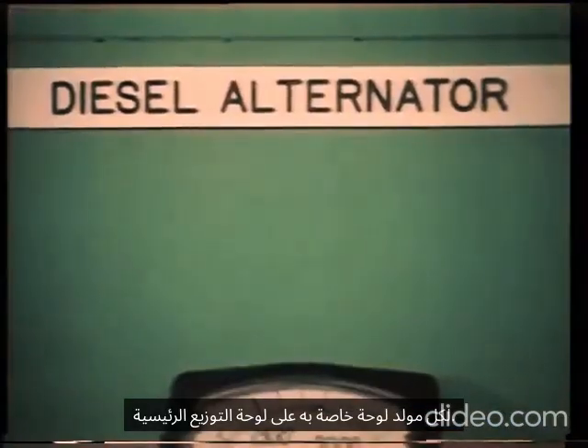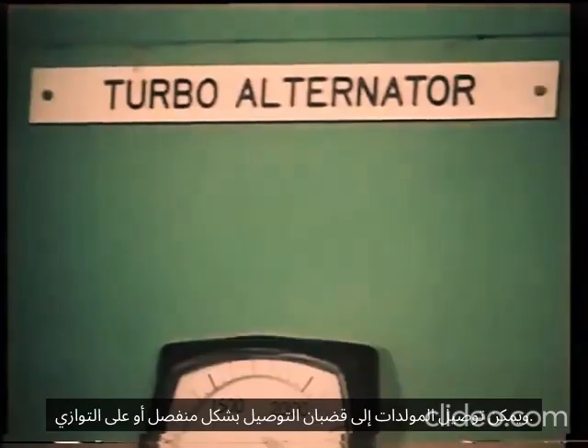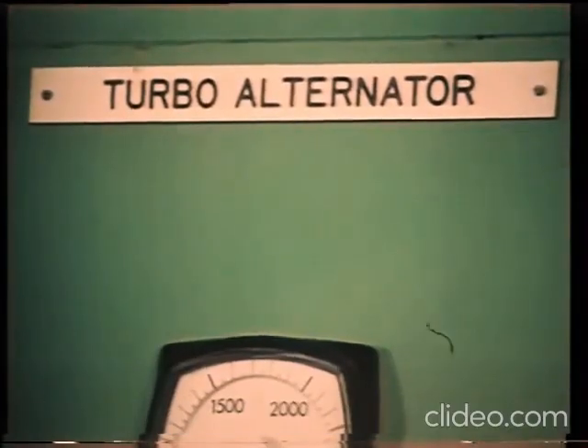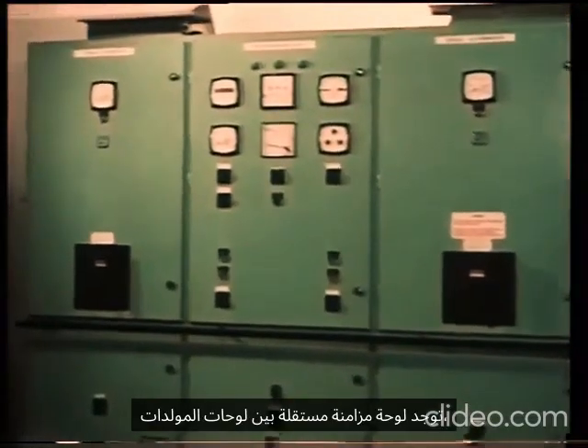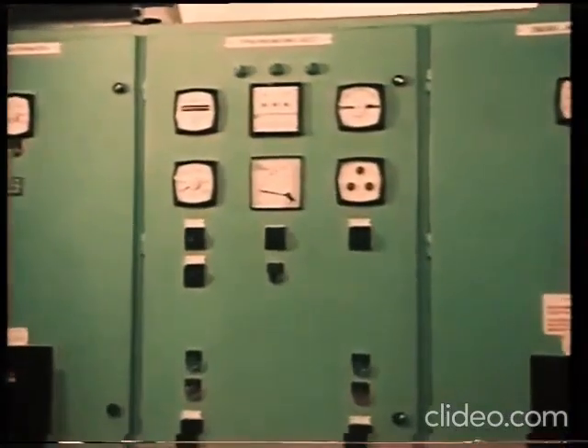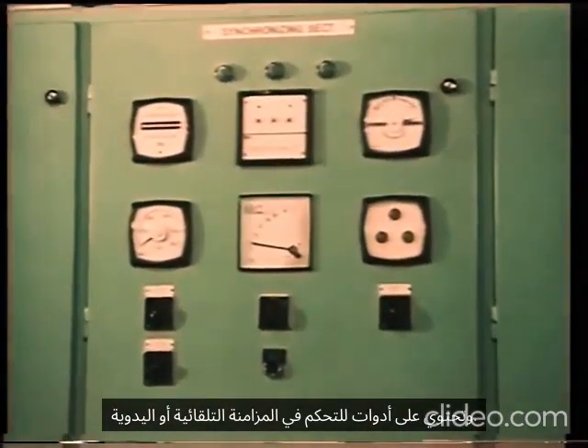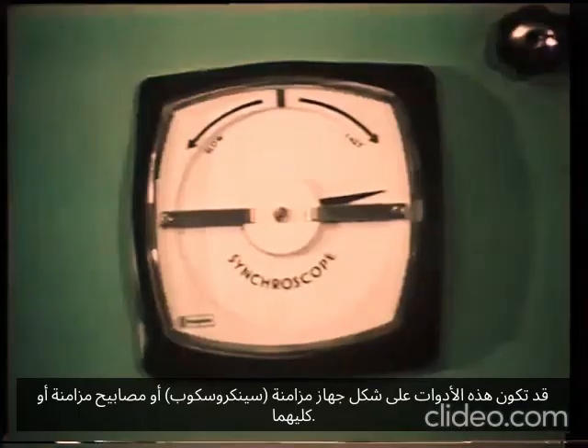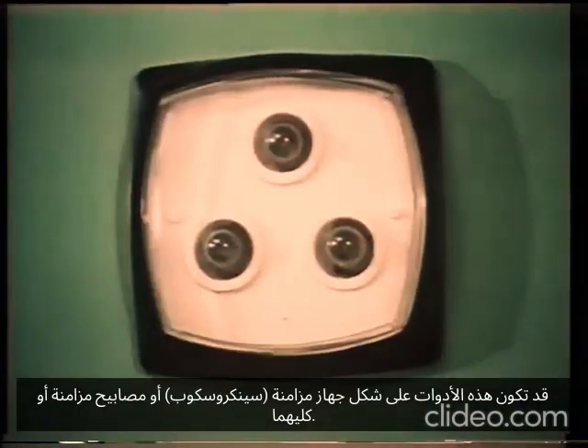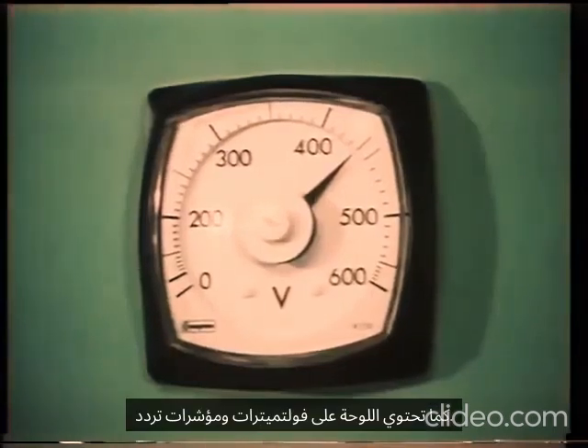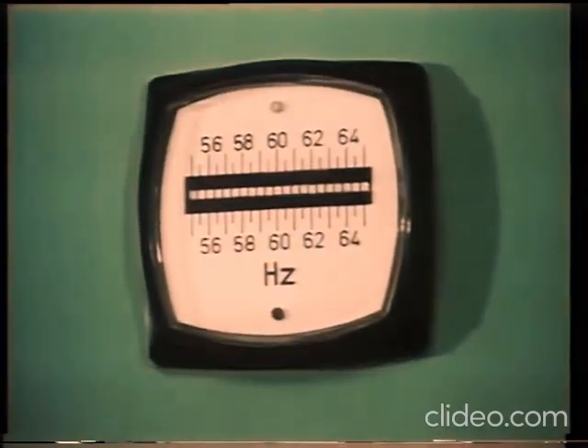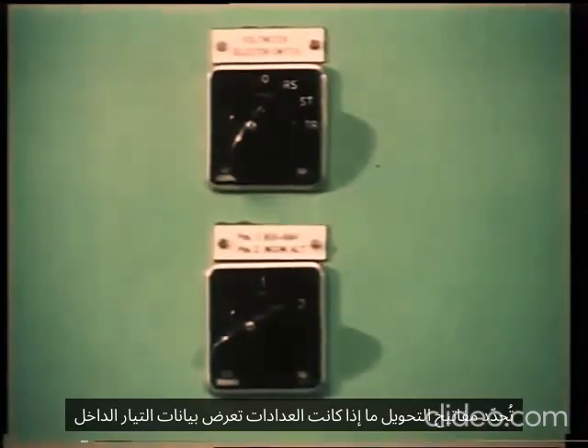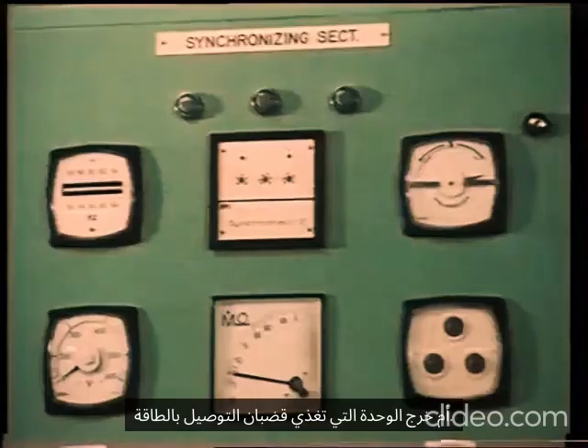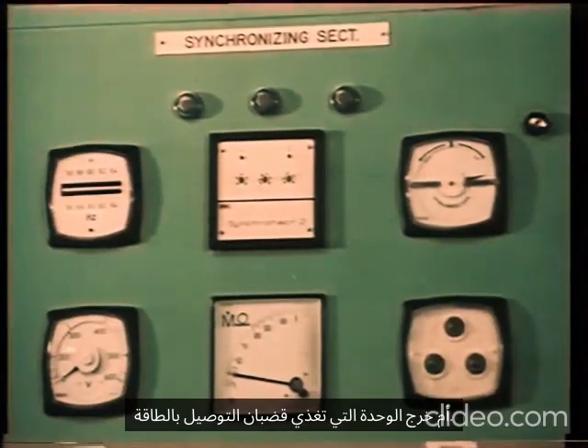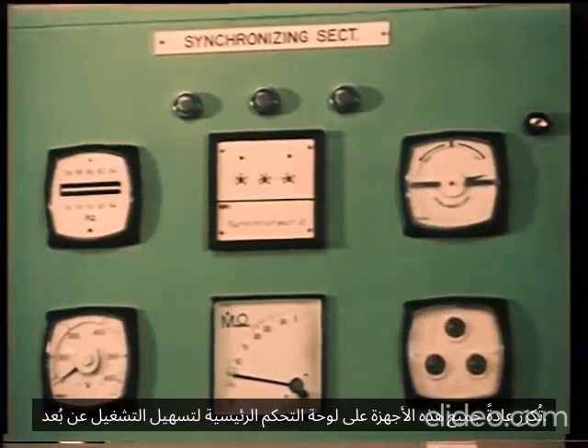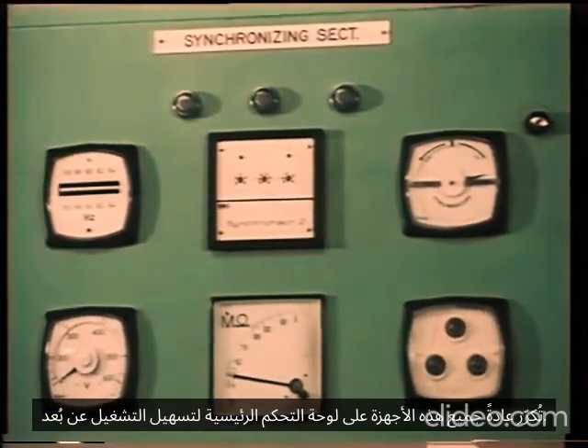Each alternator has a panel on the switchboard, and the alternators can be connected to the bus bars separately or in parallel. A separate synchronizing panel is located between the alternator panels, which has controls for auto-synchronizing or for manual synchronizing. These may be either a synchroscope or synchronizing lamps, or both. In addition, the panel has voltmeters and frequency indicators. Changeover switches determine whether the meters show the incoming data or the output of the unit supplying power to the bus bars. All these instruments are usually duplicated on the main control console for remote operation.